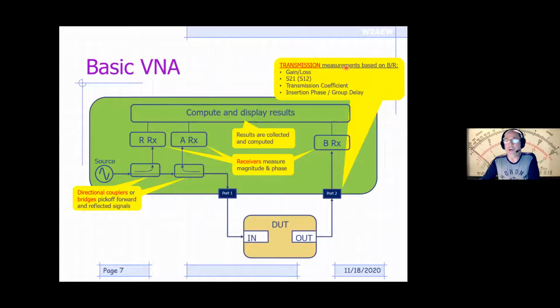So the transmission properties, again, are based on this ratio of the signal measured in the B receiver compared to the reference receiver. So we're sending out a signal, we know what that reference is, the B receiver is what's being transmitted. So that ratio, B over R, is essentially the transmission properties of the device. What does this output look like compared to what was applied at the input? So that could be looking at something like gain or loss through that device. It could be looking at an S parameter called S21. It's also called the transmission coefficient. We'll talk about what that is and define that for you. And then also could be looking at the insertion phase or group delay through a device.